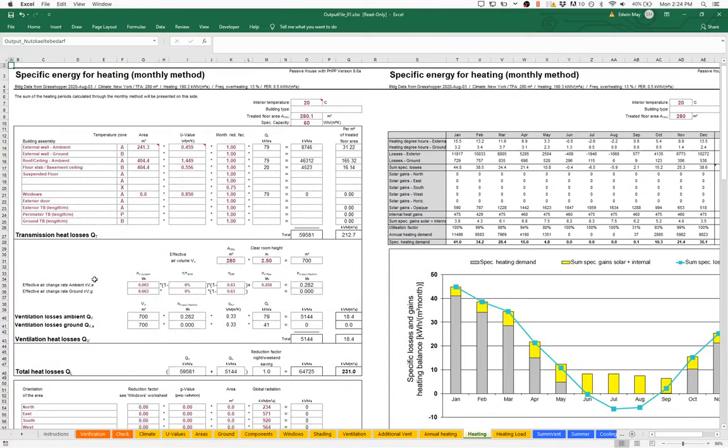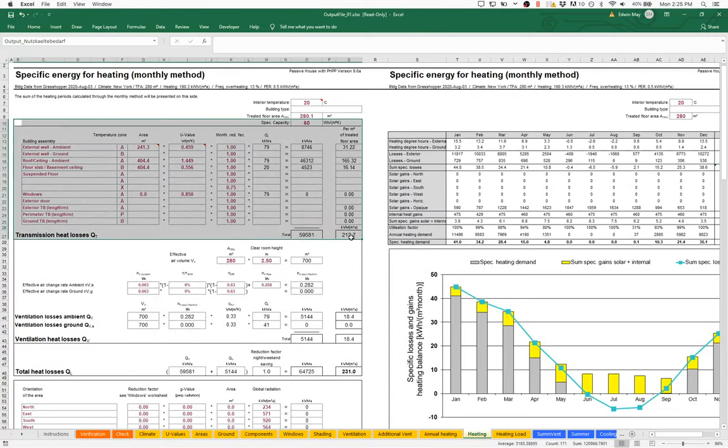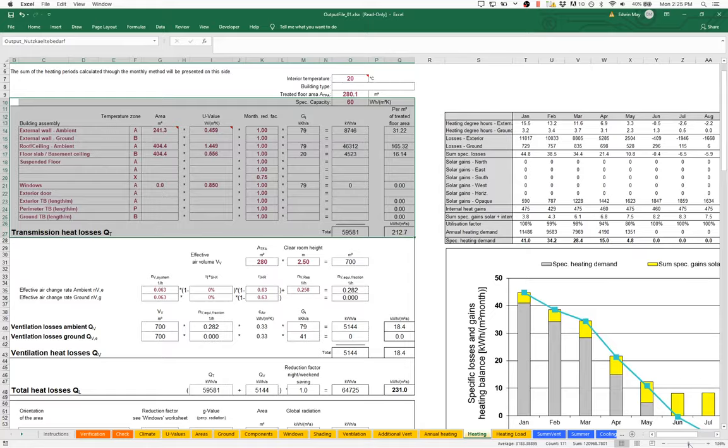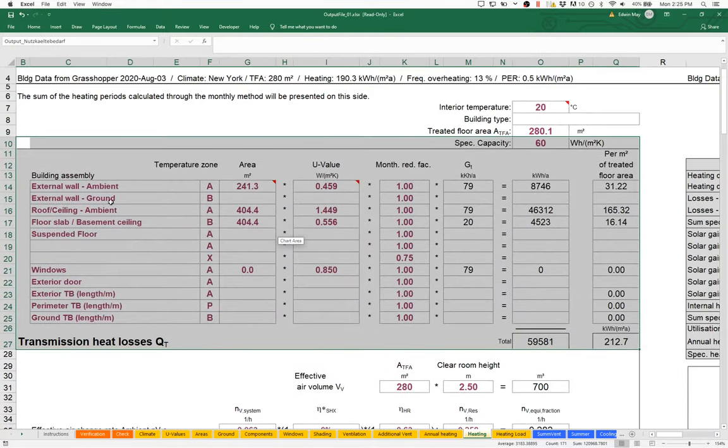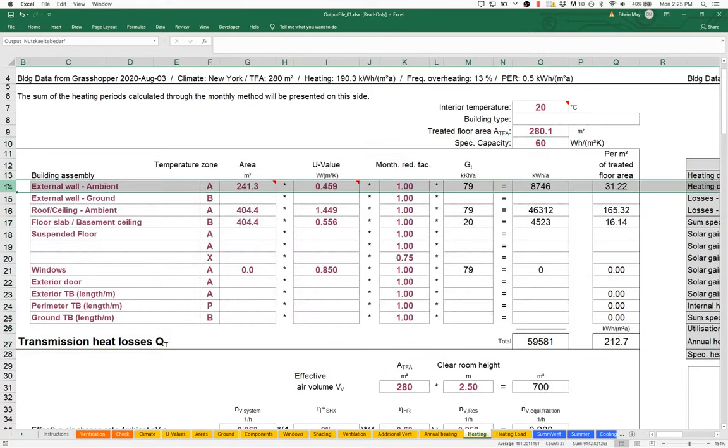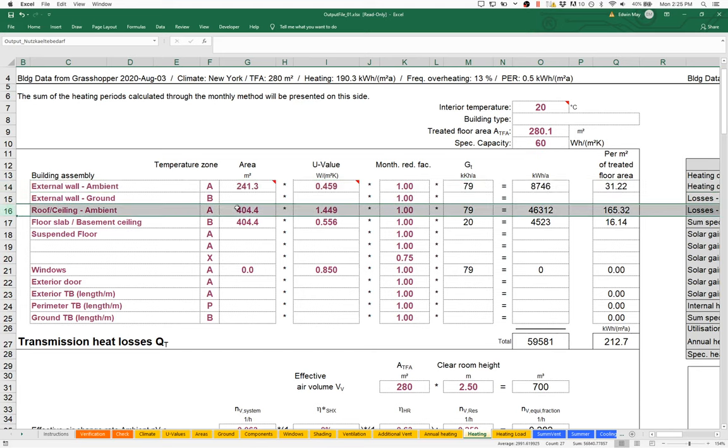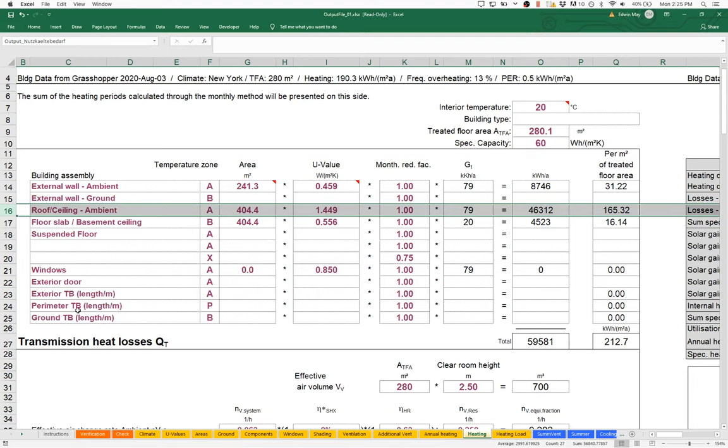If we come up to our transmission loss panel here, let me zoom in so we can see that easier. Here's our transmission loss data. Our exterior walls have some area with a U-value of 0.45 - pretty bad, but not catastrophic. That gives us a total heat loss over the course of the wintertime. Then we have our roof. Our roof has an area and, oh my, look at the U-value here: 1.4. Really, really poor U-value, which is going to result in a very high heat loss over the course of the wintertime. And we have our floor slab with kind of a not very good U-value as well. We don't have any windows, doors, or thermal bridges in the project yet. But just from this information, I can see that there's something weird happening with the roof. The roof has a very high U-value associated with it for some reason.